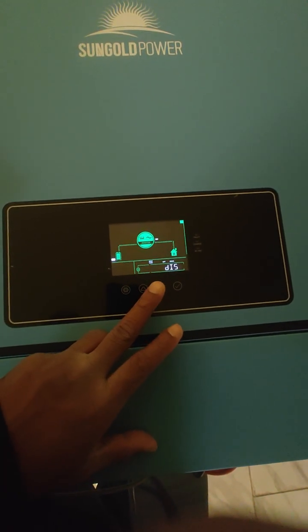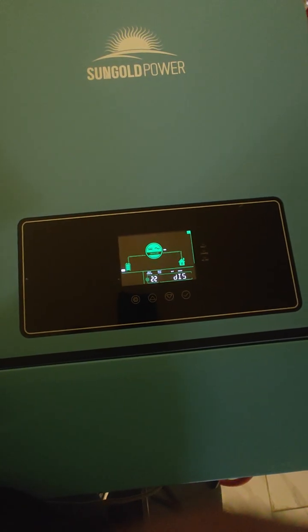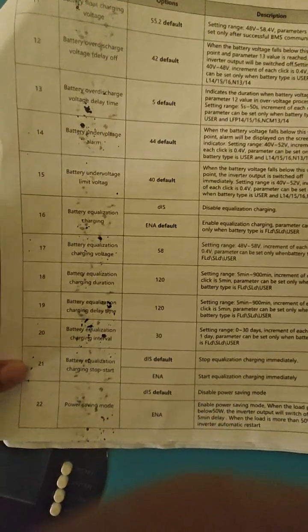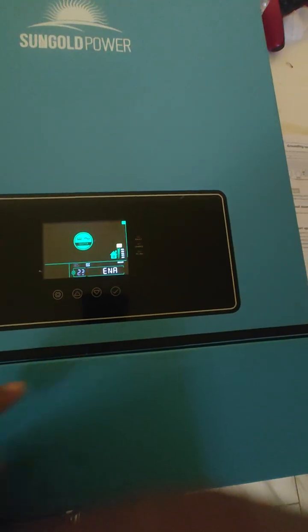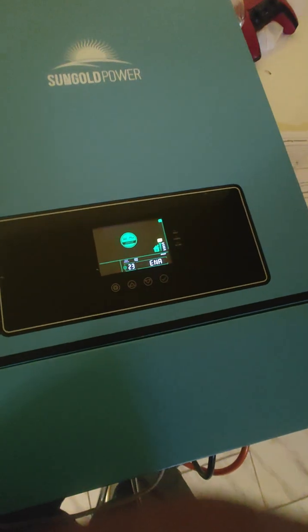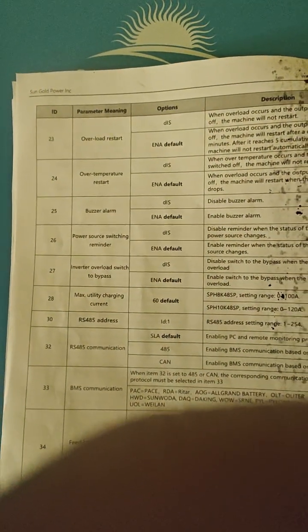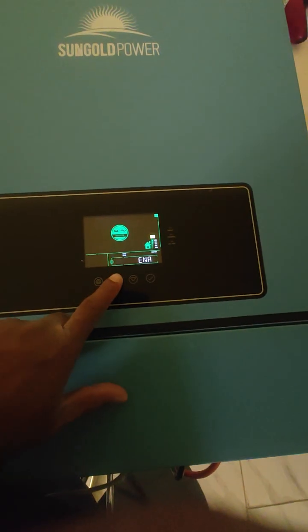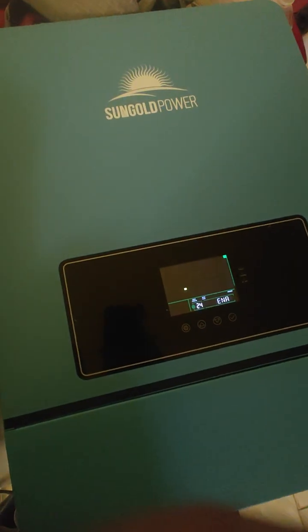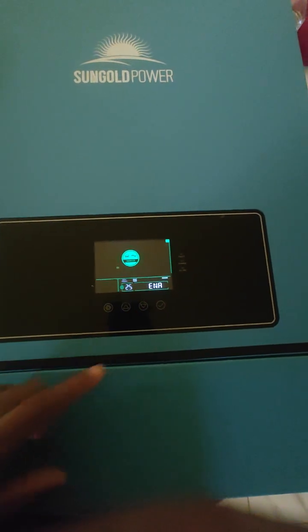16. Oh, I went from 15 to 22, so skip 15, 16, 17, 18, 19, 20, 21. 22 is power saving mode. Set disable, okay. 23 is the overload restart. Enable is fine. 24 is over temperature restart. That's enable is fine. 25 is the buzzer alarm. Guess that's fine.